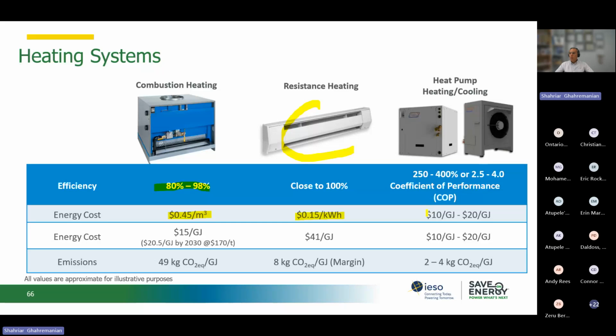If we install a heat pump with a typical COP of 2.5 to 4, it's going to cost us $10 per gigajoule and up to $20. This row is the better one to compare because the other has a different unit, so we cannot compare those directly. If we run our combustion heating system, it's going to cost us $15 per gigajoule. If we run resistance heating, it's going to cost us $41 per gigajoule. And the heat pump is going to cost us $10 up to $20 per gigajoule. So now we can compare the heat pump with the combustion heating system we have.